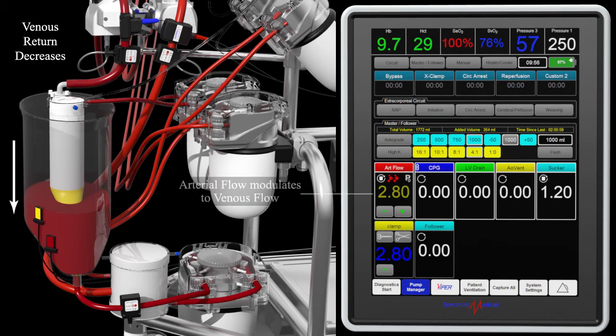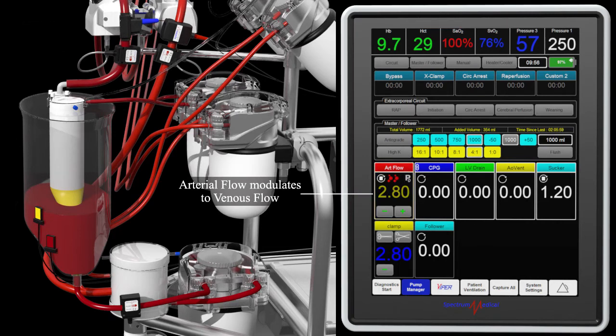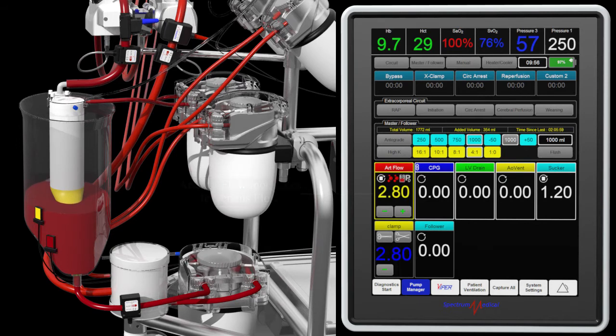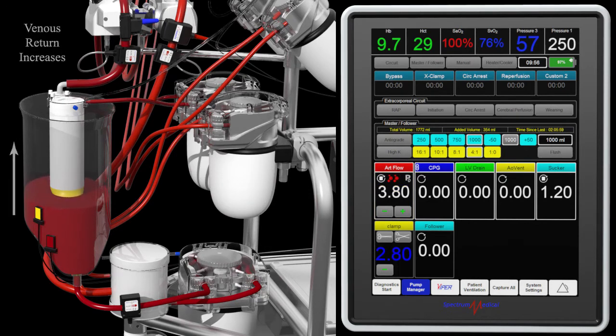Balancing venous return with arterial flow will stabilize the reservoir fluid level. Either an increase in venous return or a fluid level that recovers the yellow level sensor will allow the arterial flow to resume its original target.